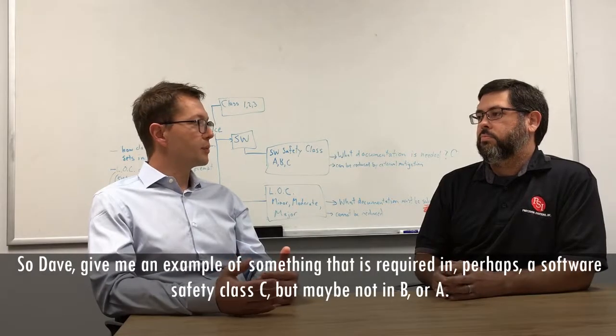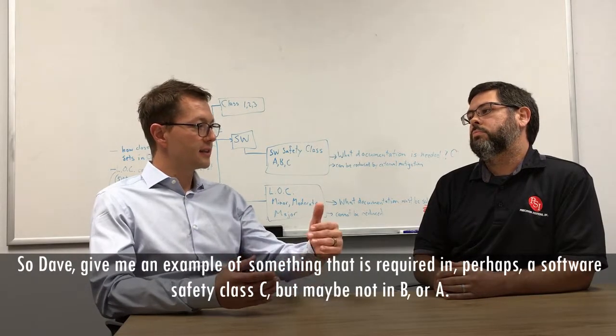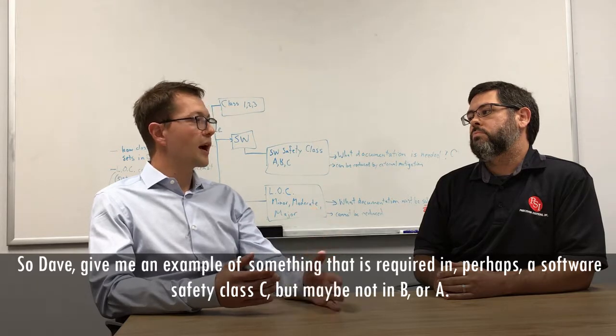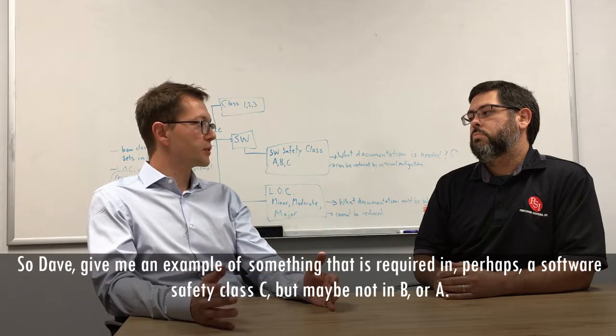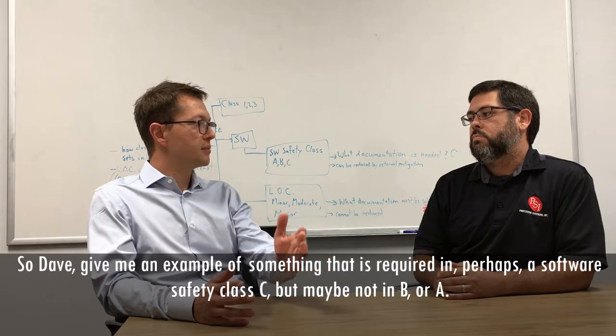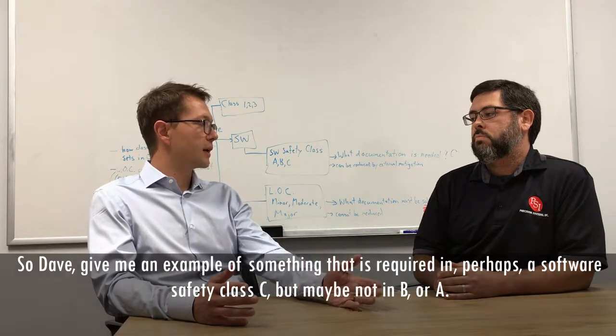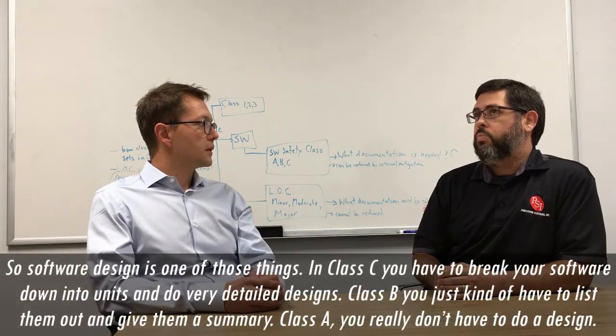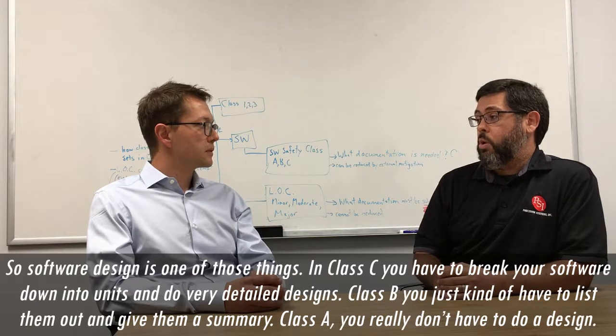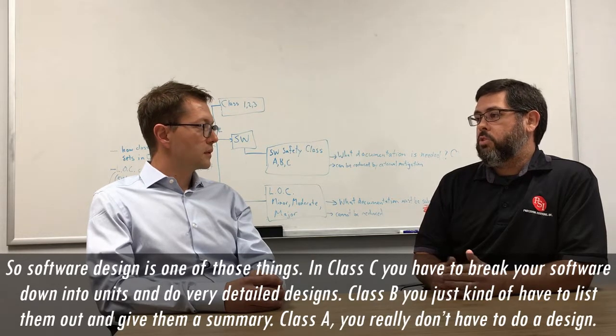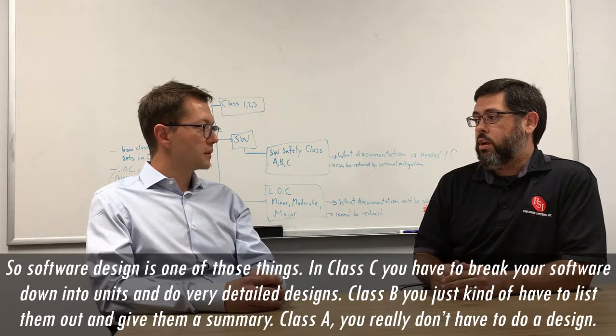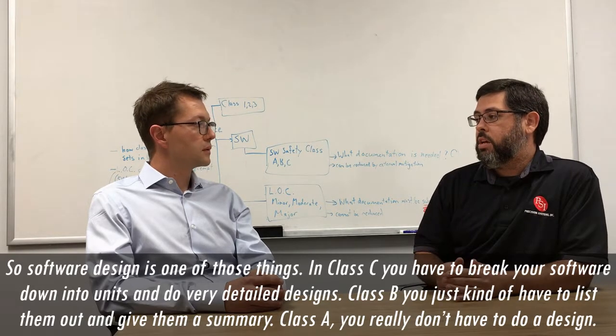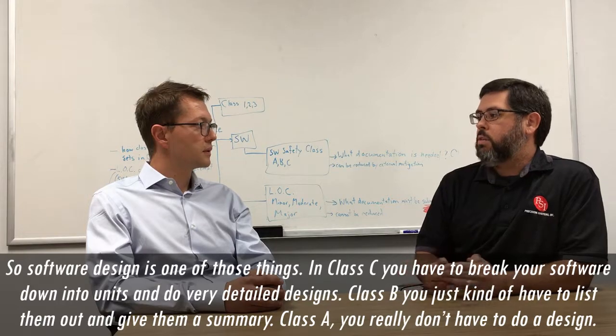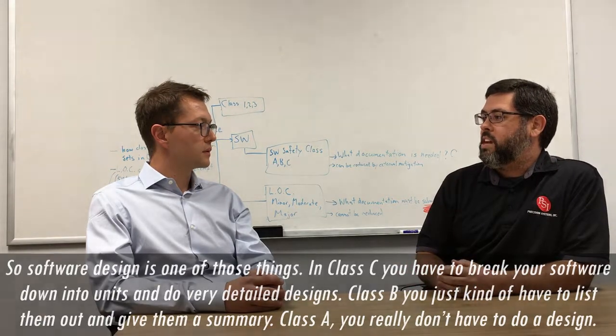So Dave, give me an example of something that is required in perhaps software safety Class C, but maybe not in B or A. Right. So software design is one of those things. In Class C, you have to break your software down into units and do very detailed designs. Class B, you just kind of have to list them out and give a summary. Class A, you don't even really have to do a design.